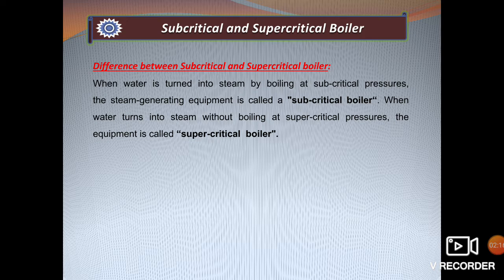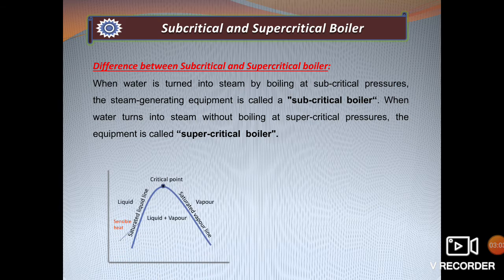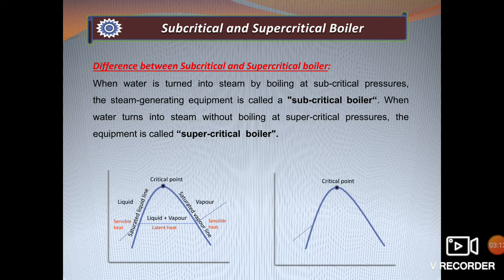To understand subcritical and supercritical boilers, we first need to know what a critical point is. From thermodynamics, we are familiar with the vapor dome — to the left is the saturated liquid line, to the right is the saturated vapor line, and the point where these two lines meet is called the critical point. At this point, pressure is 220 bar and temperature is 374 degrees Celsius. When water is converted into steam, it first takes sensible heat, then latent heat, and then again sensible heat. For example, if water is boiled at atmospheric pressure, the heat gained from atmospheric temperature to 100 degrees Celsius is sensible heat.